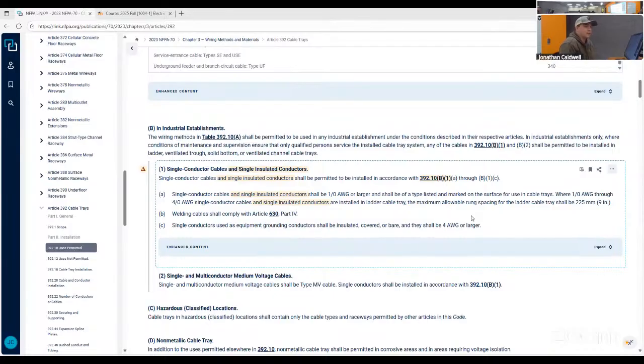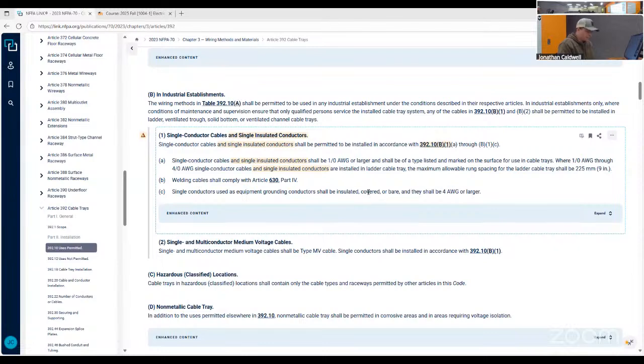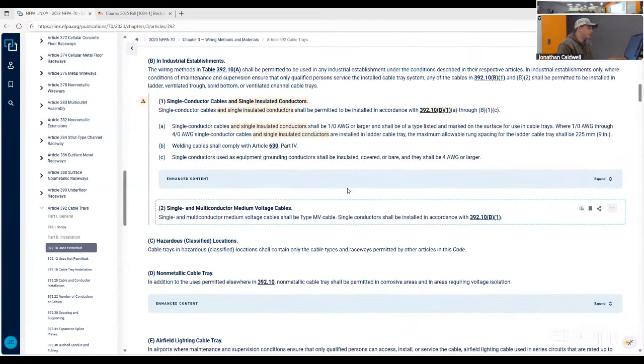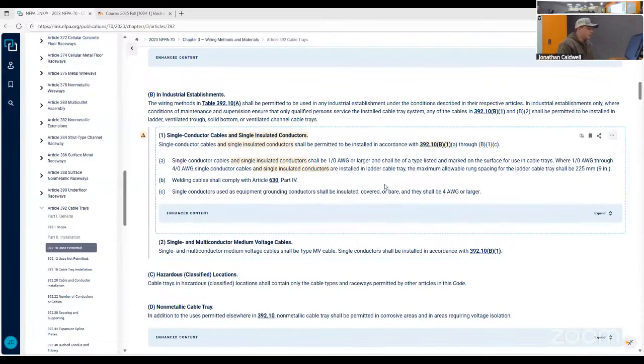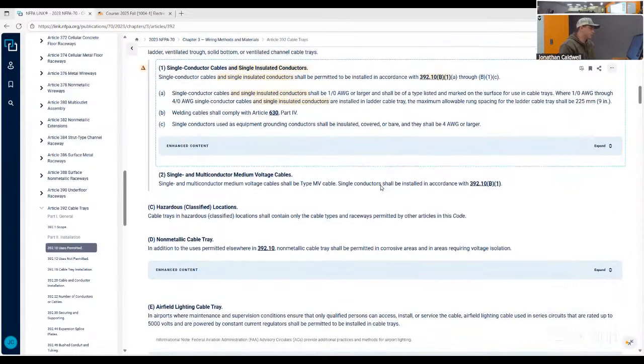Black is the only color that is sunlight resistant for any single conductors, and also the minimum size that manufacturers make sunlight resistant single conductors in is number 8. So anything below number 8 is not sunlight resistant. Keep that in mind. That's a good guess on the XHHW. XHHW is definitely, I would say, sunlight resistant, doesn't matter the color, but the manufacturer does not put on the color for XHHW that it is sunlight resistant. And especially for THHN. That's why when you see an overhead line, it's always black. Only black for this.